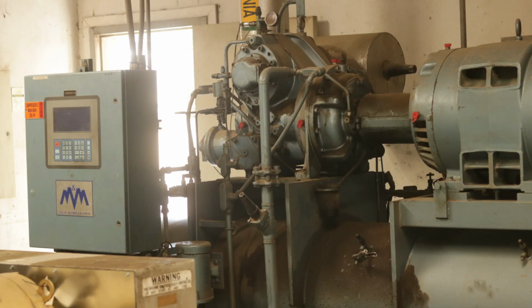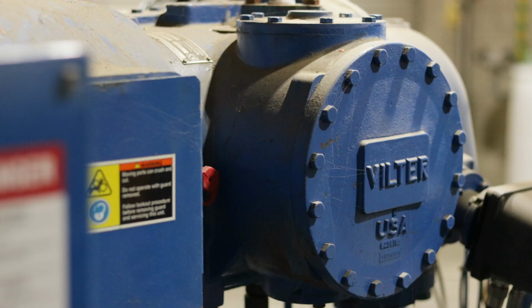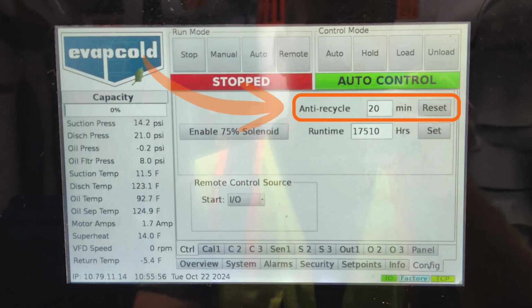A motor is supplied with excessive current at startup. This is called in-rush current. Because of this, repeatedly starting and stopping a compressor is not recommended and will result in premature motor failure. The anti-recycle timer protects a motor from this by preventing the motor from starting for a predetermined duration of time after being shut down. For screw compressors, the anti-recycle set point may be between 10 and 30 minutes.